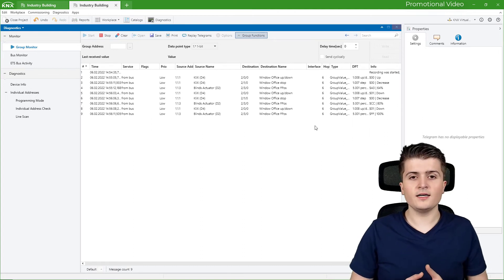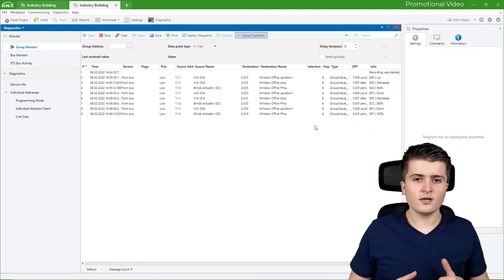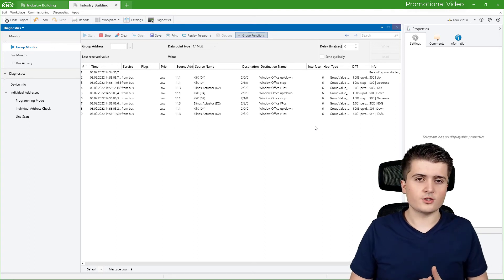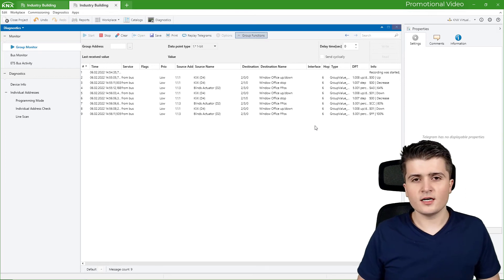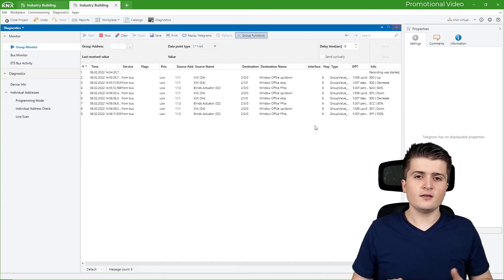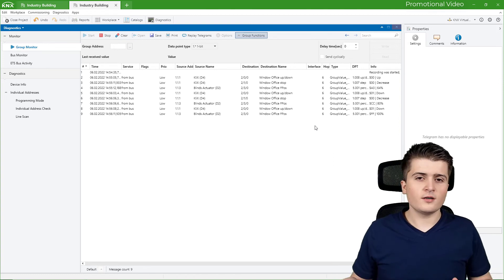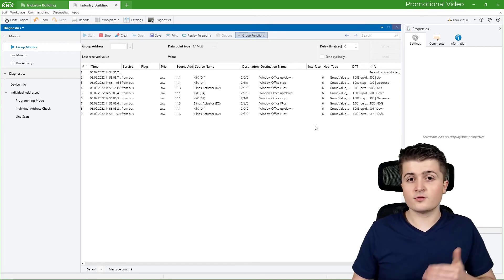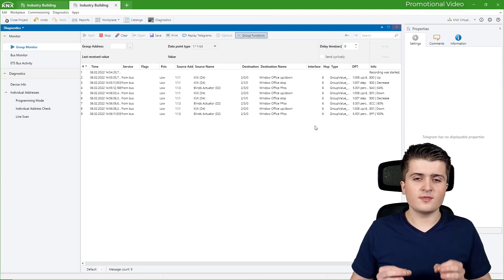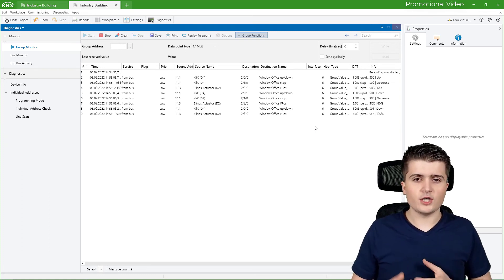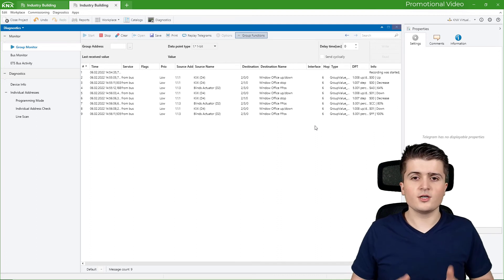You'll notice that the blinds only update their position feedback after the movement has finished. This is the normal behavior for real blind actuators. If a building has many blind actuators and a storm is detected causing all blinds to move simultaneously while each sends periodic position updates every second, the 50-telegram-per-second limit on twisted pair would be reached very quickly. Therefore the default setting is to send the feedback only once after movement completes, though some actuators allow periodic updates.